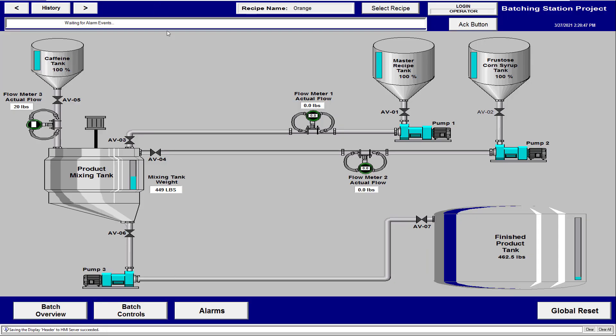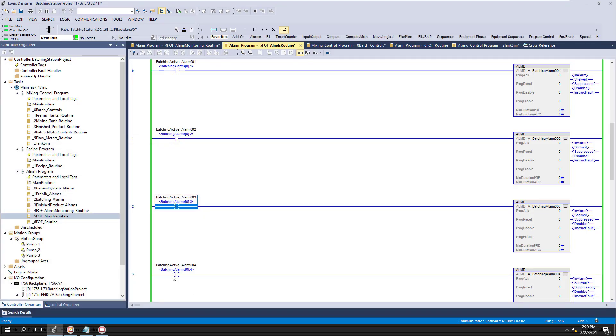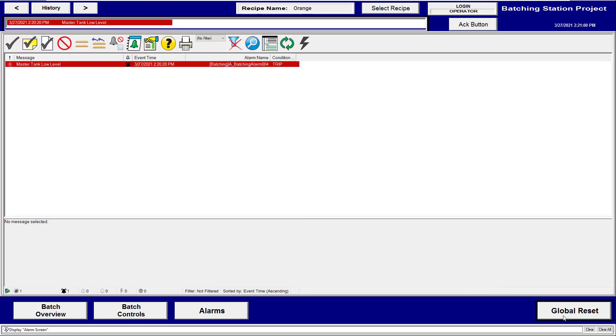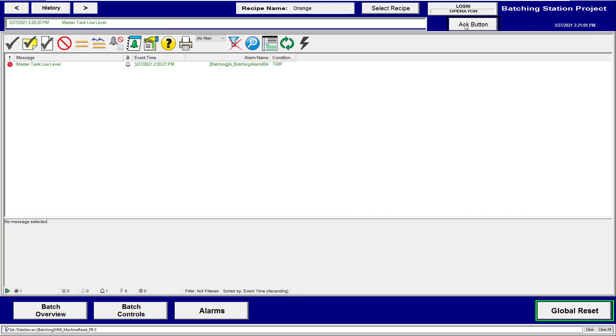Let me show you that one more time with the alarm summary. We'll do another alarm — let's say alarm four. Alarm four is on, let's go to the alarm page, reset it, and instead of using the alarm reset or acknowledge, we're going to hit this VBA button. That closes it all out just that simple. That button didn't call any commands or write to any PLCs — it used the VBA code in the back of the application to achieve that goal. Hopefully that was helpful. We'll see you on the next one.